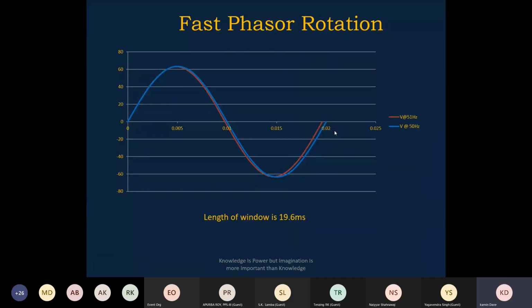So this is how you see the fast phasor rotations at 50 hertz. The phasor has to be readjusted according to the 50 hertz component. That is called frequency tracking. Otherwise, we will get wrong frequency values in that case.